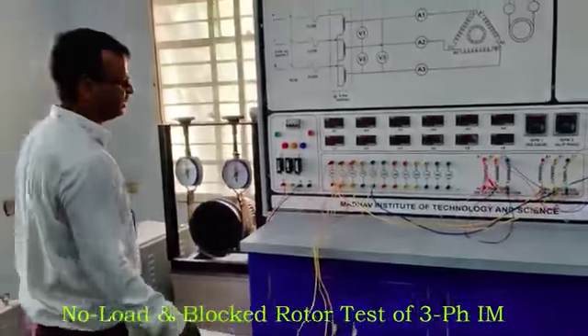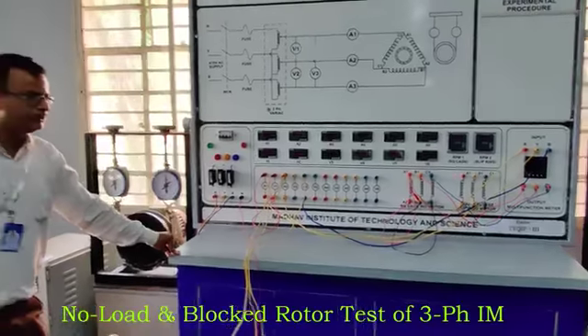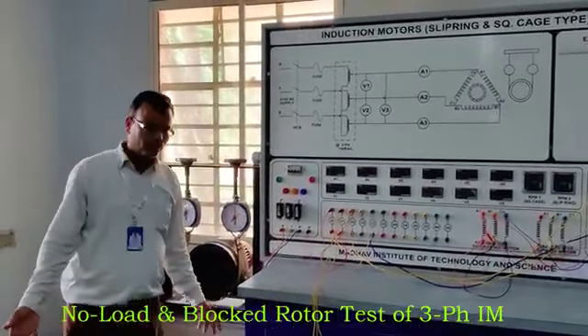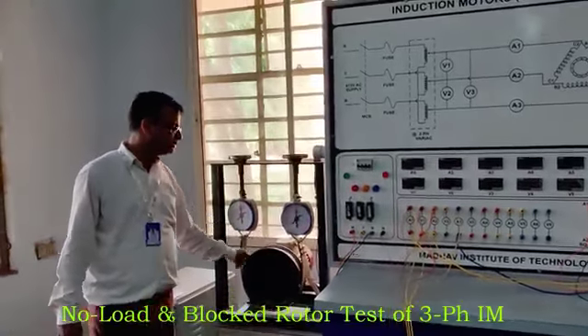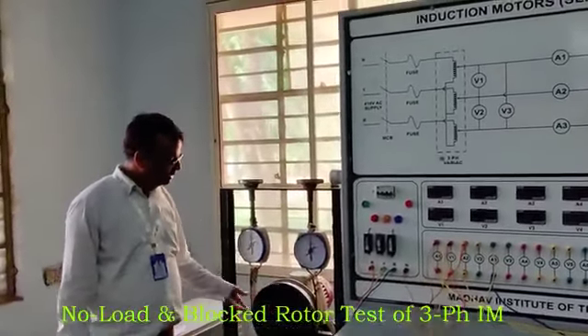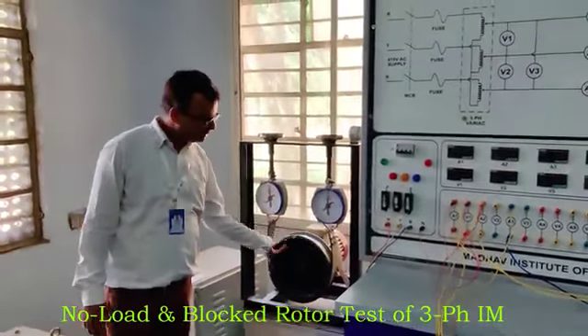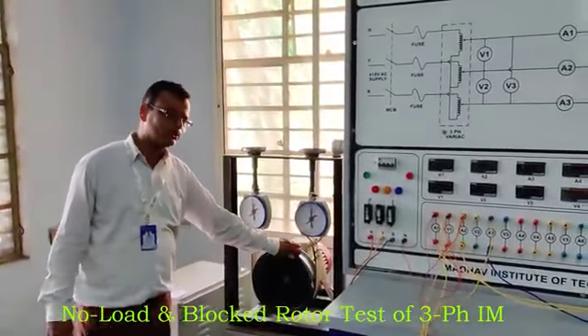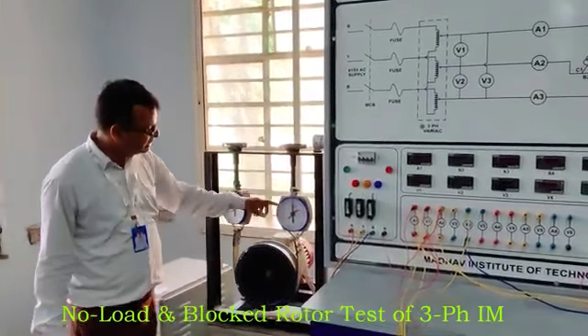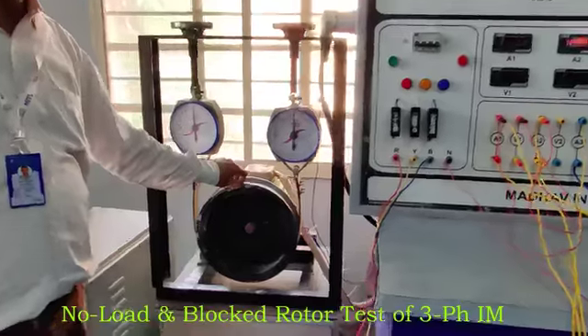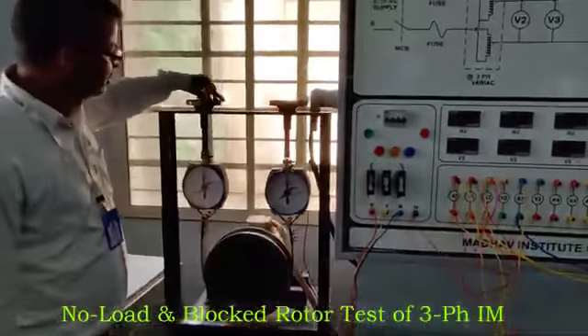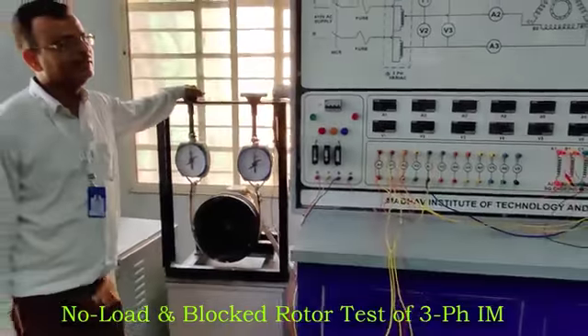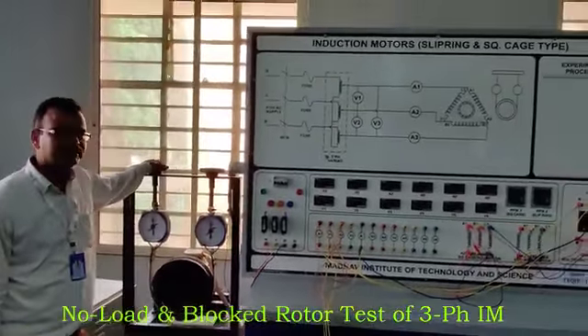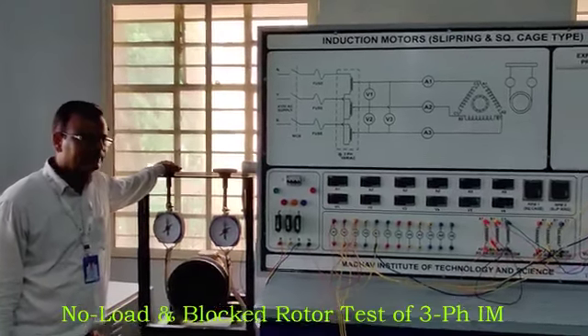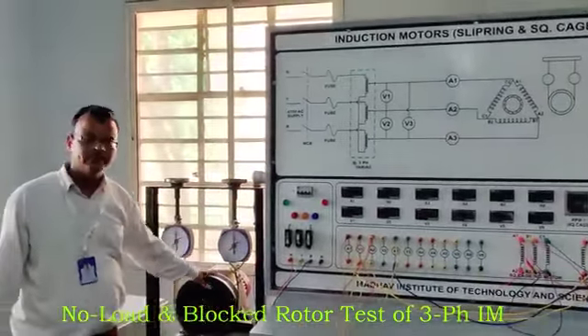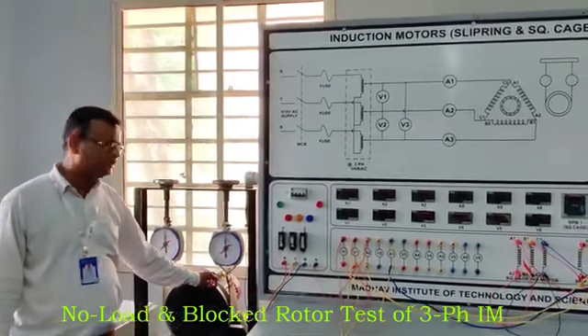Second step, after doing the connections, we will perform the no load test. No load means no load is connected on this pulley. Just allow this pulley to rotate freely. No mechanical load is applied here. That's why it is called the no load position. Second, we have already studied in the theory part of this experiment that this test is performed at rated voltage. The rated voltage of this machine is 415 volts and the rated speed is 1500 RPM.